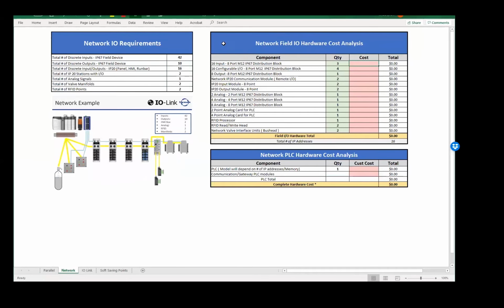So on the network, we still have the same number of inputs, obviously, on the left. Yep. So this is where it did some auto calculation for us, which is very nice. So traditionally, we're not going to use an input-only block, so zero that out. Okay. We're going to put all our field devices, our IP67 devices, in a configurable I.O. block. Okay. In this case, Ethernet IP. So we have 42 plus 10 of the outputs, 52. So we're going to need 4 16-point I.O. configurable blocks. And we'll say an Ethernet IP block nowadays is around $400.